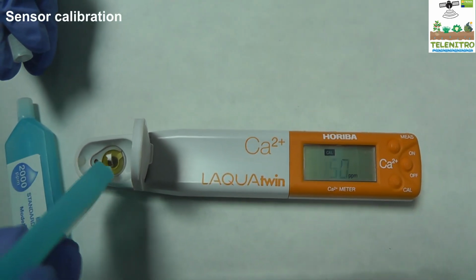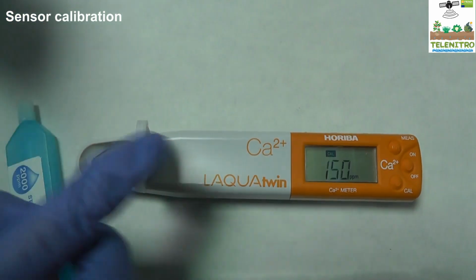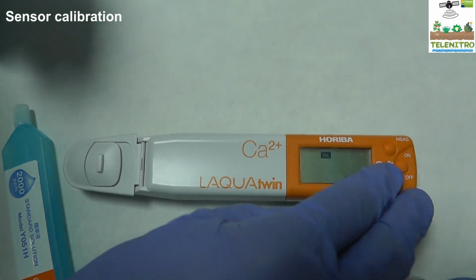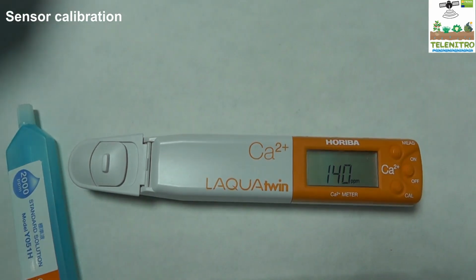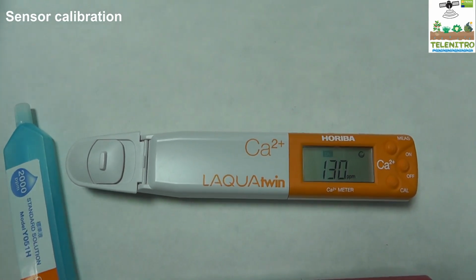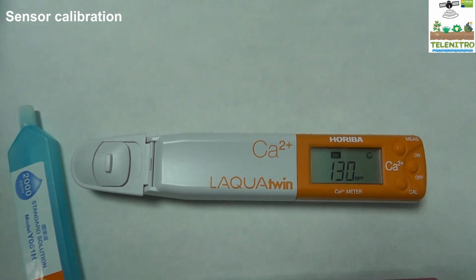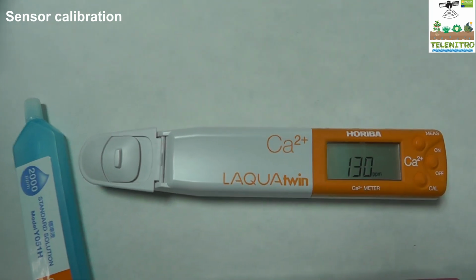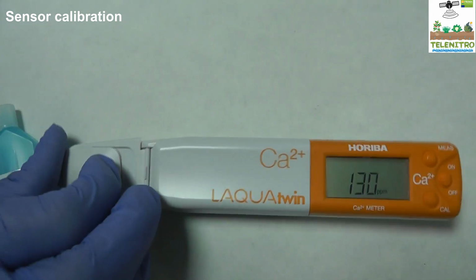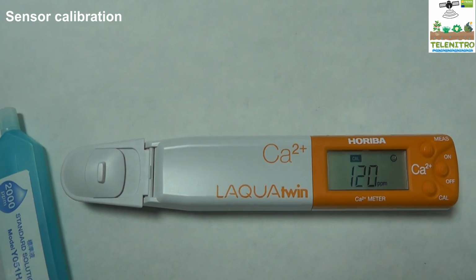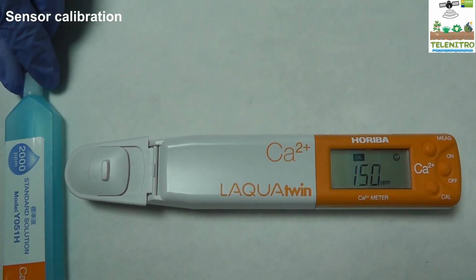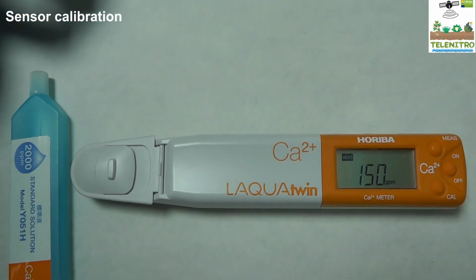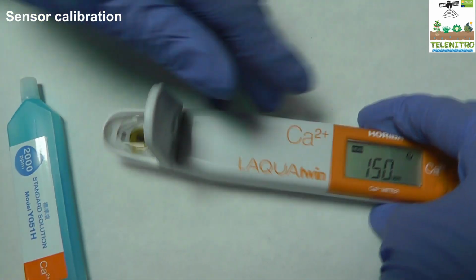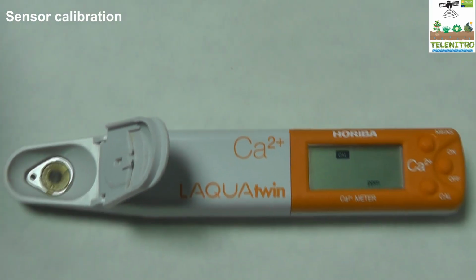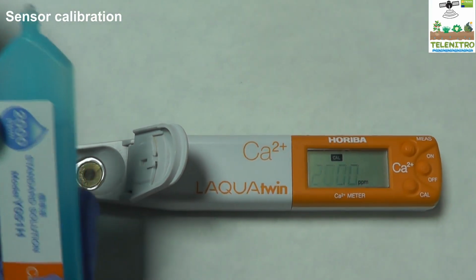First, the standard solution of lower concentration is added to the sensor until it is completely covered, the opaque lid is closed, and the cal button is pressed for 2 seconds. The cal symbol flashes on the screen along with the calibration value. Once the calibration for the low concentration is complete, the standard solution is removed, the sensor is rinsed with distilled water, and dried with filter paper before calibrating with the high concentration standard solution, repeating the same process.